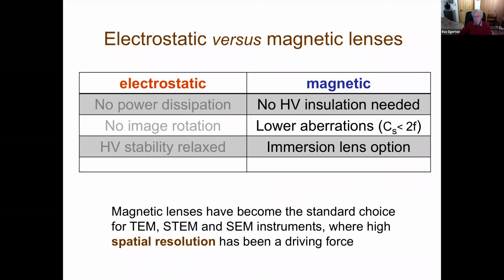And this is important in connection with what we call the objective lens in either a TEM or a STEM instrument. It's the lens closest to the specimen, and it's the lens that determines more than the other lenses the spatial resolution of the whole instrument. And so if we have a focal length of the order of a millimeter, that means that the specimen has to be within a millimeter or two of the center of the lens. So really, the specimen is in the lens field, in the magnetic field of the lens.